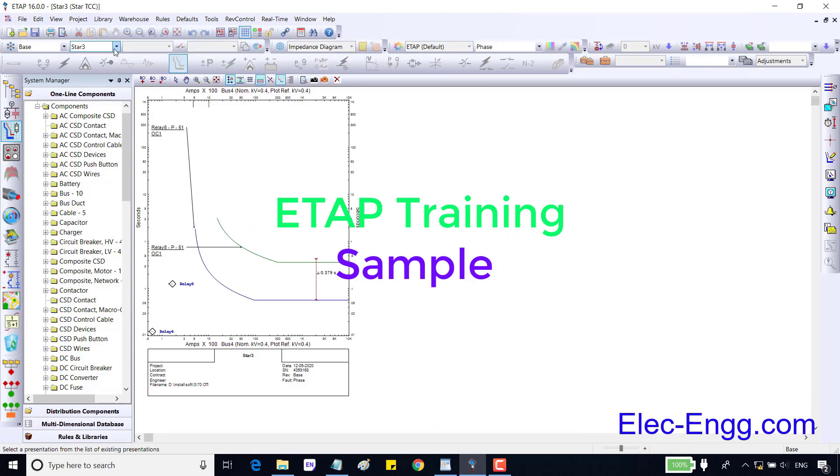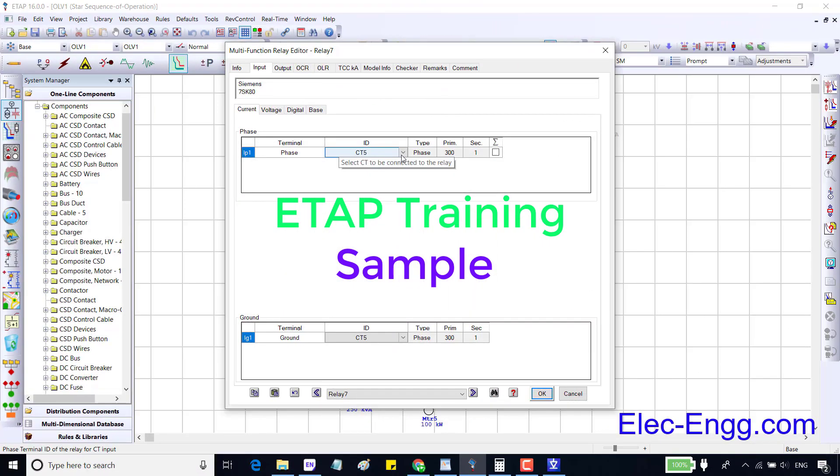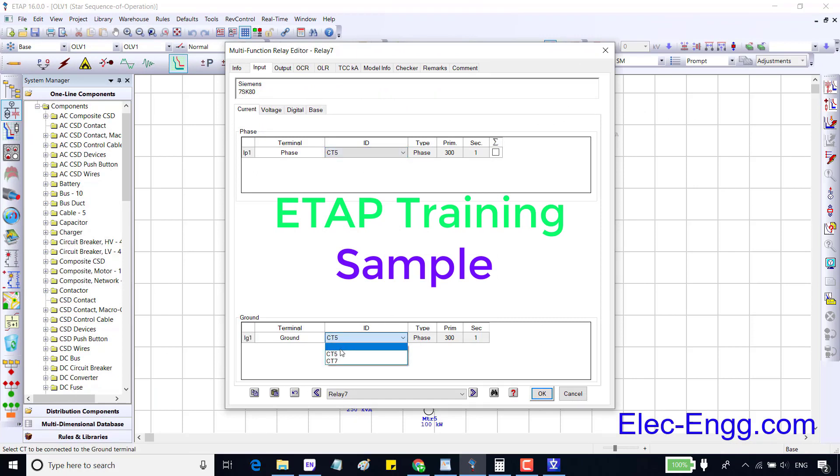In this session we are going to set the instantaneous phase overcurrent, or 50. CT5 is selected as the phase CT, but in the ground CT we can select between CT5 and CT7. CT7 is a core balance CT. These two CTs are completely different.